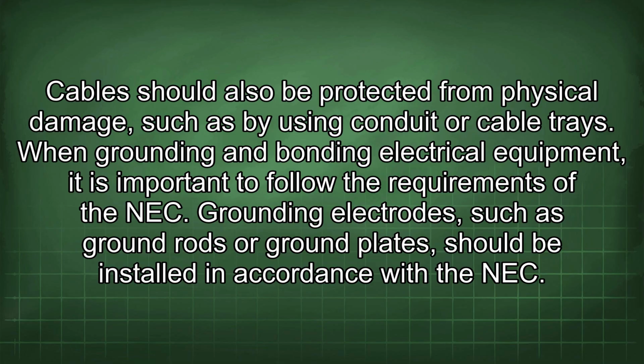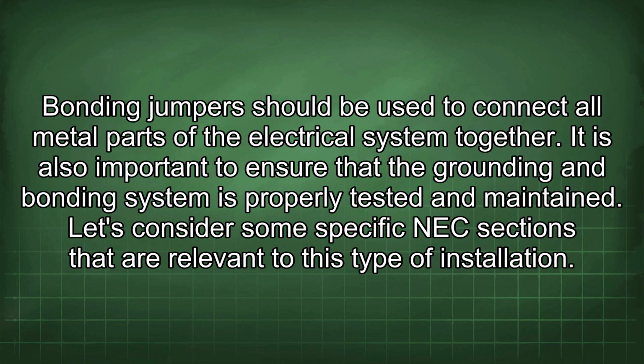Cables should also be protected from physical damage, such as by using conduit or cable trays. When grounding and bonding electrical equipment, it is important to follow the requirements of the NEC. Grounding electrodes, such as ground rods or ground plates, should be installed in accordance with the NEC. Bonding jumpers should be used to connect all metal parts of the electrical system together. It is also important to ensure that the grounding and bonding system is properly tested and maintained.